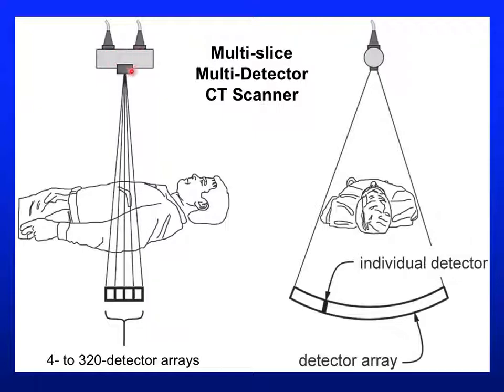Here's the geometry again. We have a source of x-rays — the x-rays come out of the x-ray tube — and they are detected on the opposite side of the patient. There are multiple detectors in Z. Nowadays you can have up to 320 detectors in the Z direction and about a thousand detectors in the theta direction — roughly a 1,000 by 320 array of detectors behind the patient. The patient casts a shadow on that detector, you take a picture of the shadow, move the angle, and take another picture — all done very rapidly.